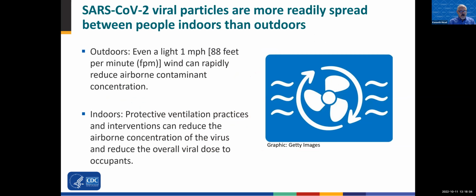Outdoors, even a light 1 mile per hour wind can be very protective. You know, 1 mile per hour, that's nothing. You will not feel 1 mile per hour outdoors. You'll talk about how dead the air is. But yet 1 mile per hour is 88 feet per minute, and that's approximately the same protective airflow that's used at the intake to a laboratory fume hood. So it works very well in rapidly reducing airborne contaminant concentration.